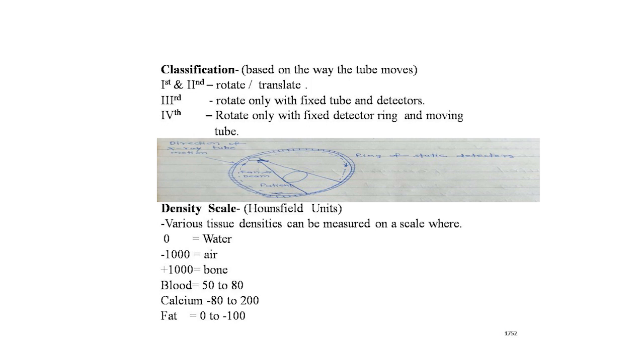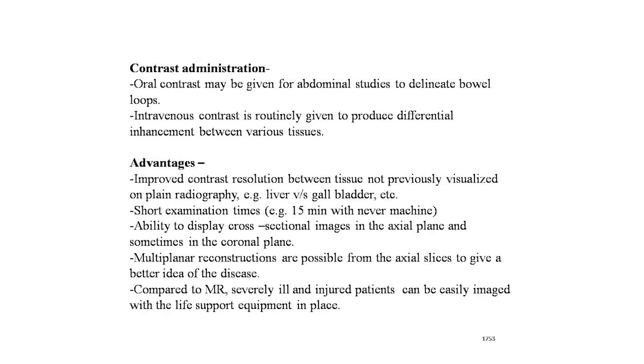CT scanner classifications based on how the tube moves: first and second generation — rotate and translate; third generation — rotate only with fixed tube and detectors; fourth generation — rotate only with fixed detector ring and moving tube. Here is an image showing the direction of x-ray tube motion and fan beam with the patient on the table and a ring of static detectors. On the Hounsfield density scale: 0 is water, minus 1000 is air, plus 1000 is bone, blood is 50–80, calcium is minus 80 to 200, and fat is 0 to minus 100.